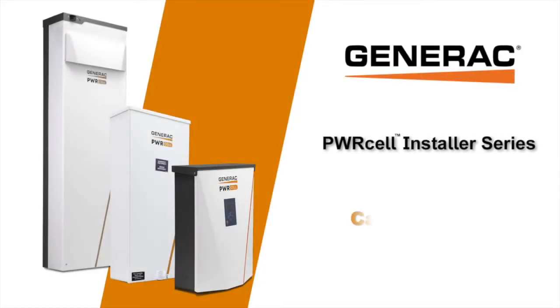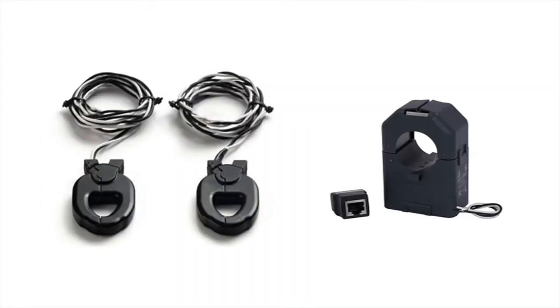In this video, we will guide you on proper placement, testing, and calibration of the included CTs. CTs are used to measure load consumption. This data will be visible in the Generac PWRview app and is essential for use of the self-supply system mode and for settings that limit import and export of power.